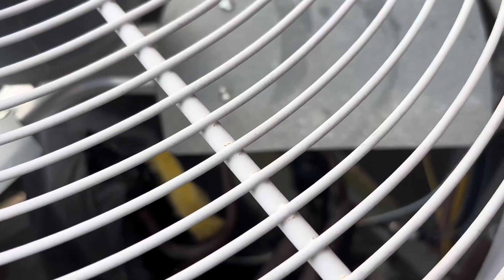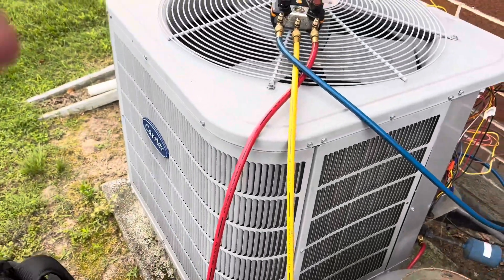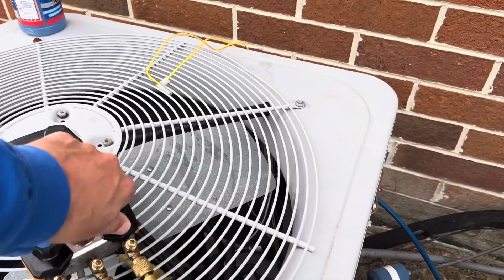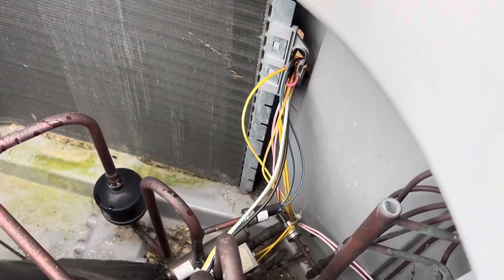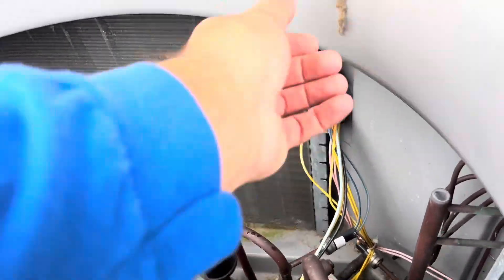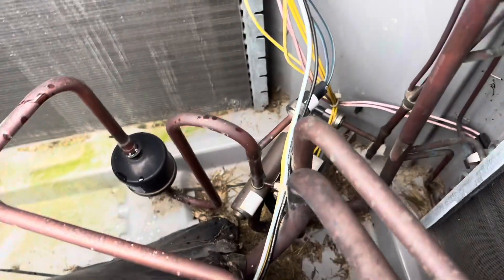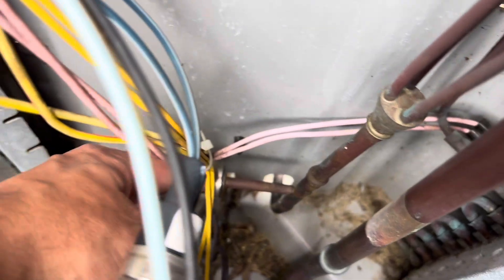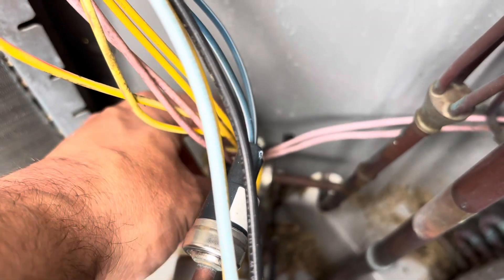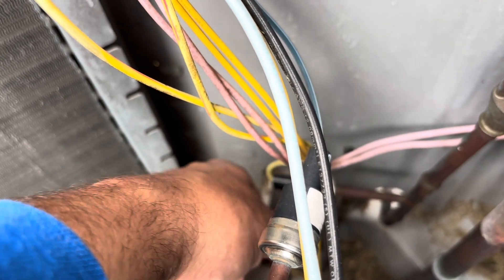We're going to replace that pressure switch with the OEM one — we're going to unsweat that and put the right one in. We're replacing the TXV too. We got the fan totally out and out of the way. Here's our suspect right here that we're changing. I'm just going to snip those wires right off and get that unsweated — not a big deal.